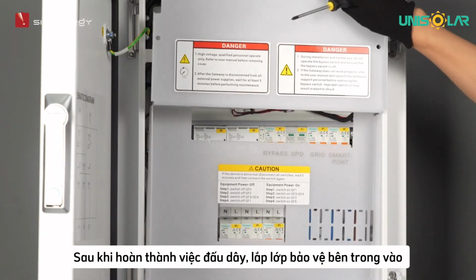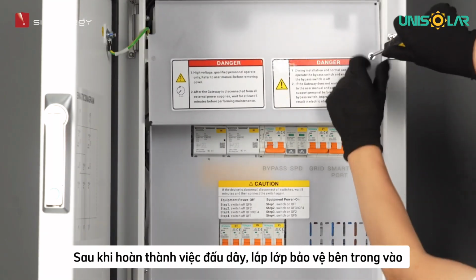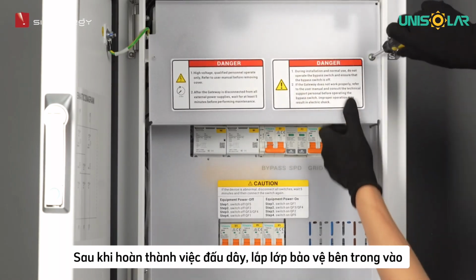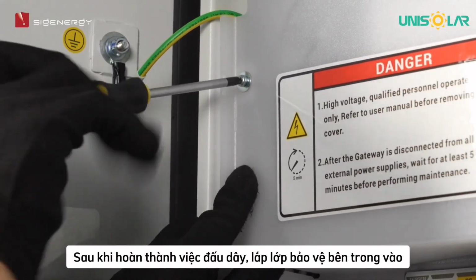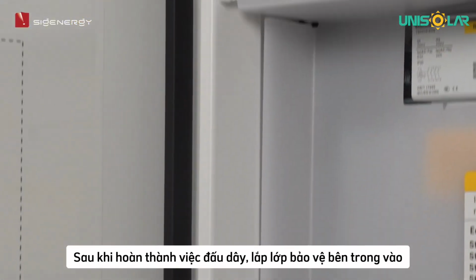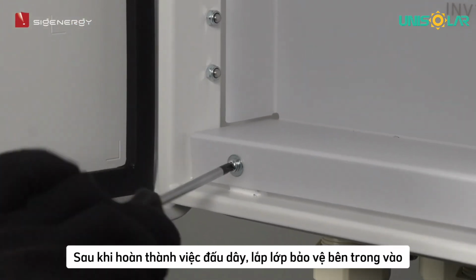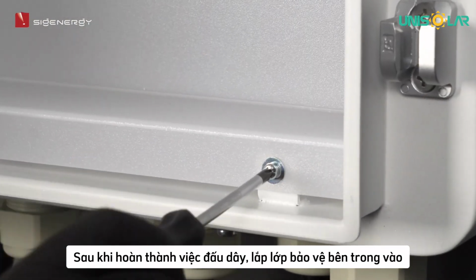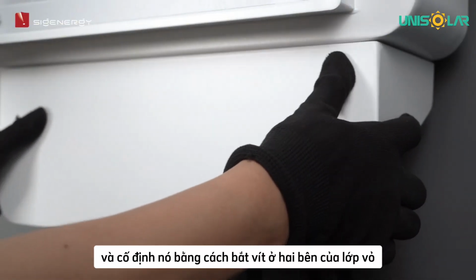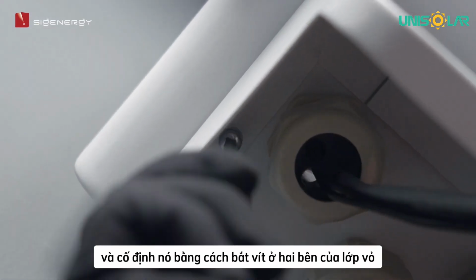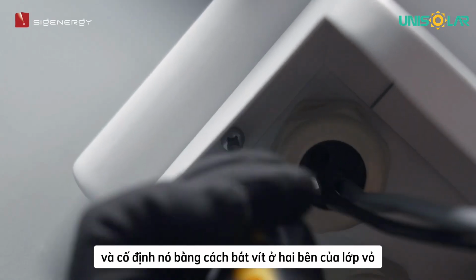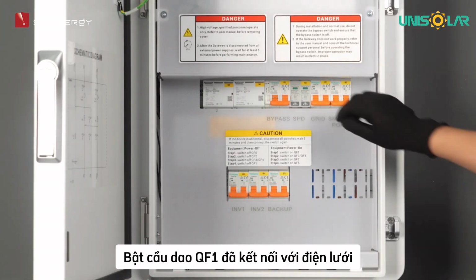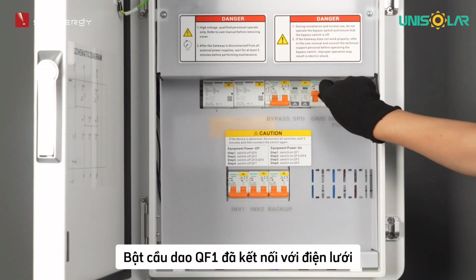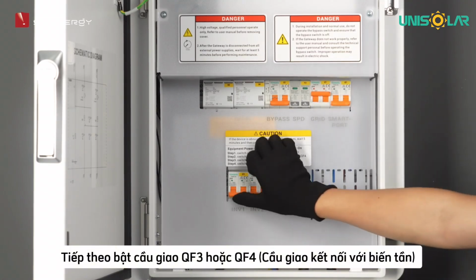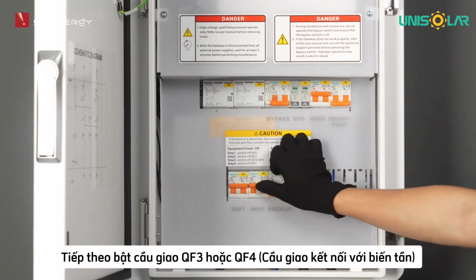Then installing the inner panel of the gateway. Install the decorative cover and fix it at the bottom of the gateway with 2 screws. Turn on the front switch of the equipment. Turn on the miniature circuit breaker QF1, connecting to the power grid. Turn on the miniature circuit breaker QF3 or QF4, connecting to an inverter.